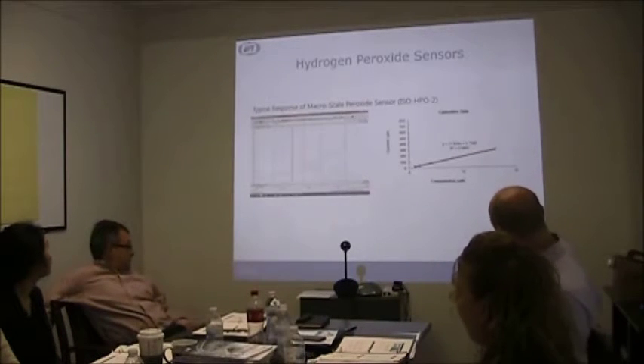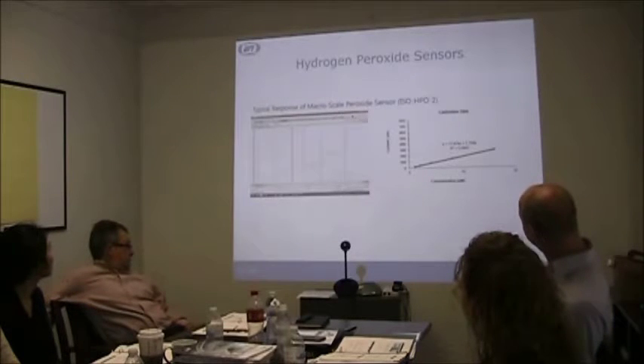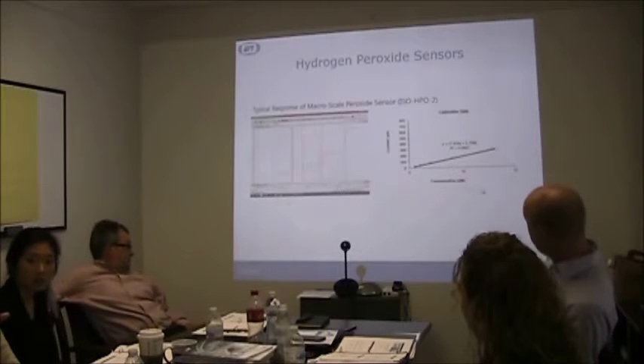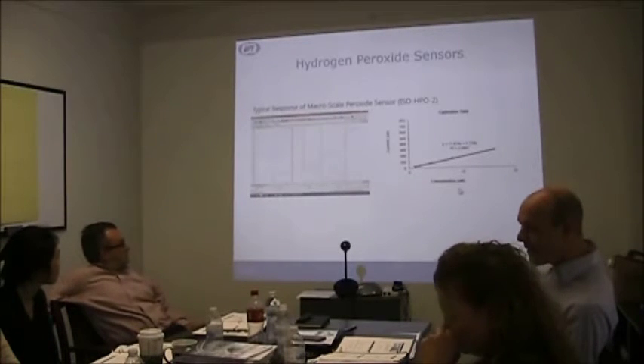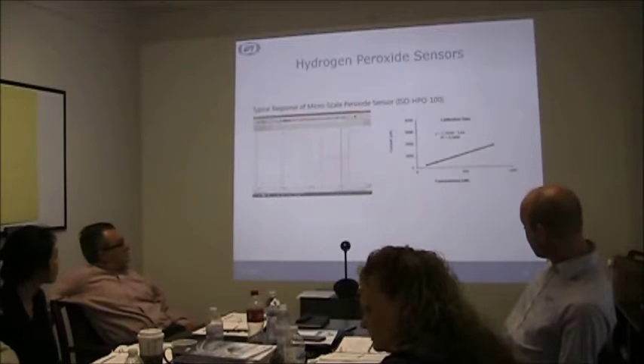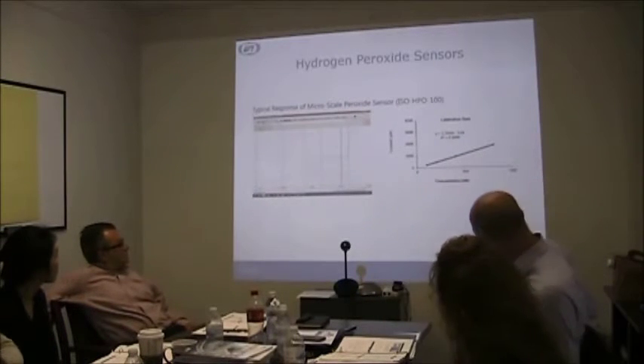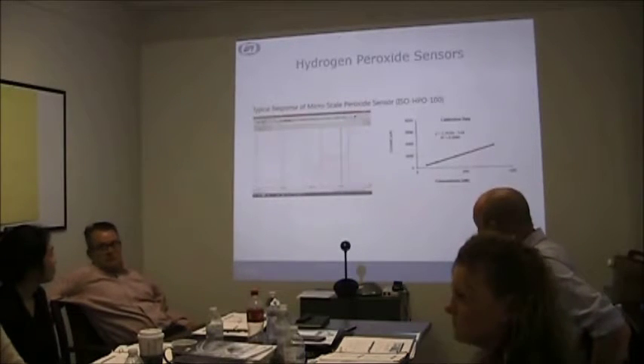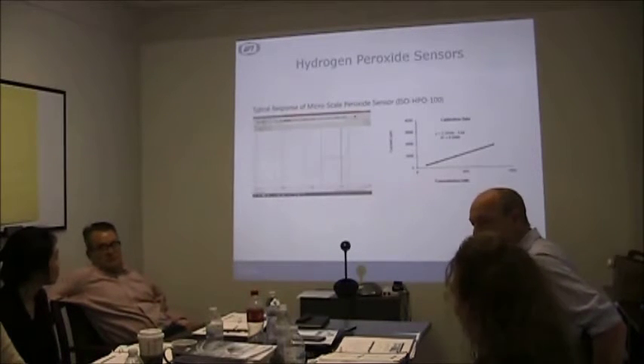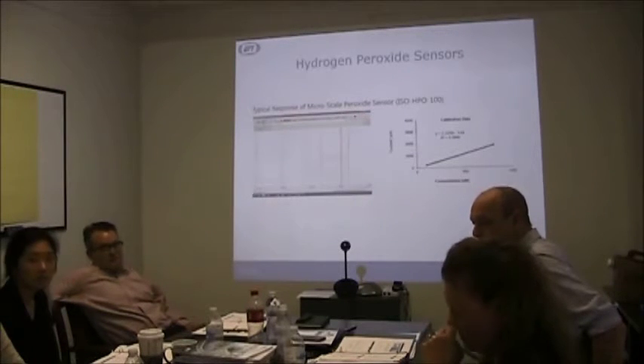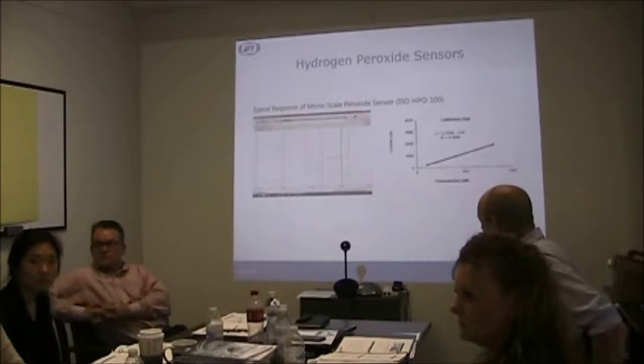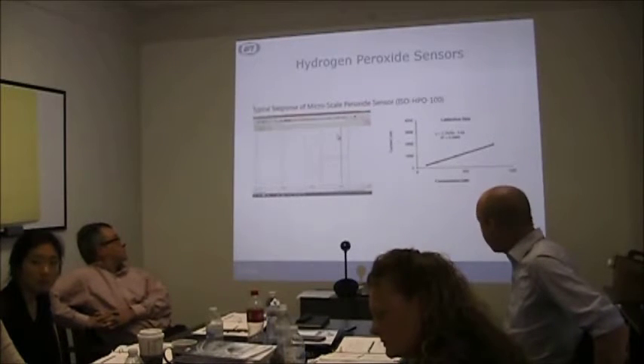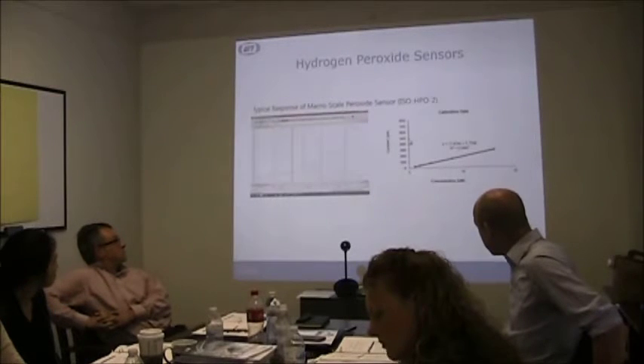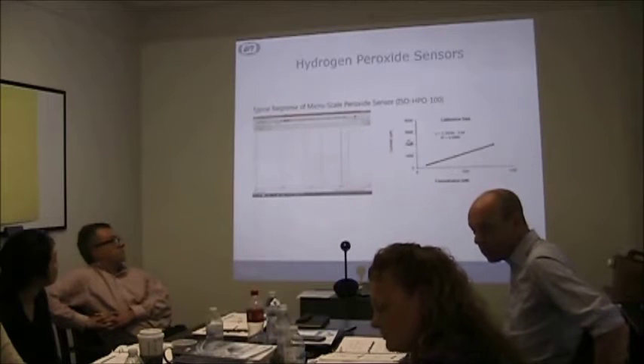Just quickly, I wanted to show here, this is a 2mm hydrogen peroxide sensor. Again, linear measurement, similar graph. But I want to point out that you see micromolar concentration on the 2 millimeter. When we go to the 100 micron, this is nanomolar concentration. They both measure hydrogen peroxide, but at vastly different concentrations. If you're advising somebody, ask what concentration they are trying to measure. If they want to measure micromolar concentration, the nanomolar sensor is not going to work well for them, so you'd want to give them the 2 millimeter version.